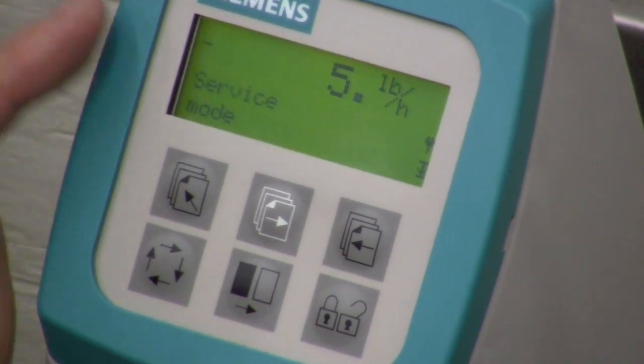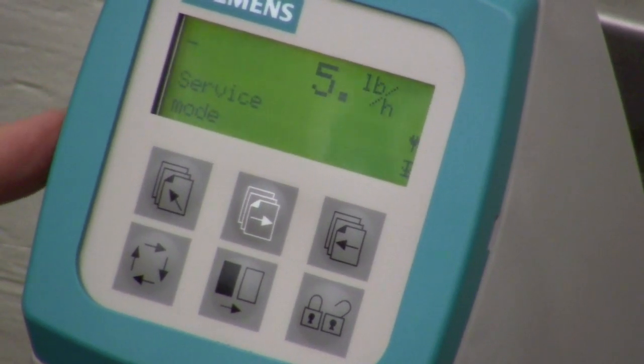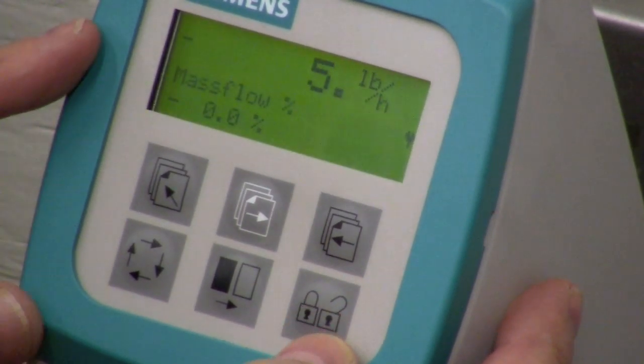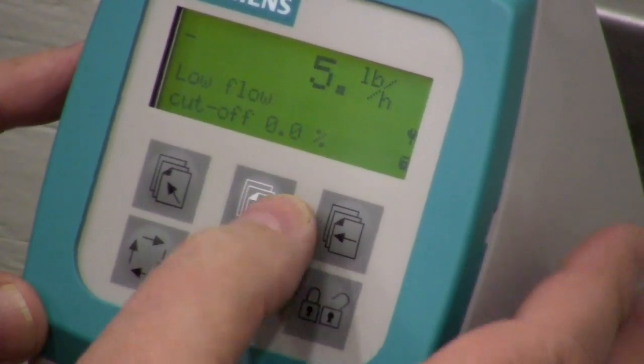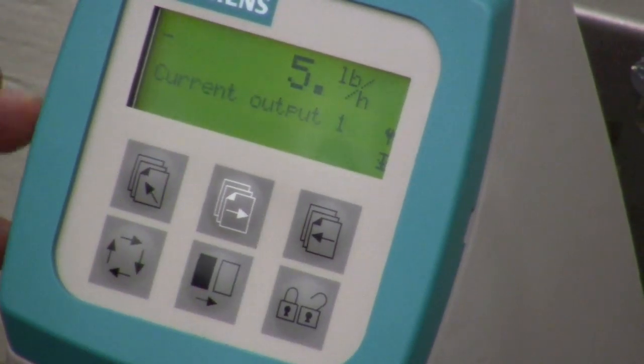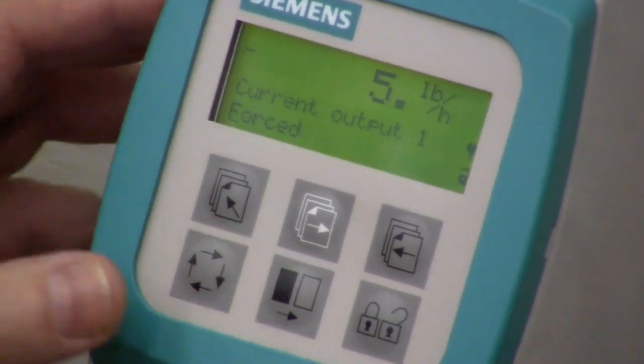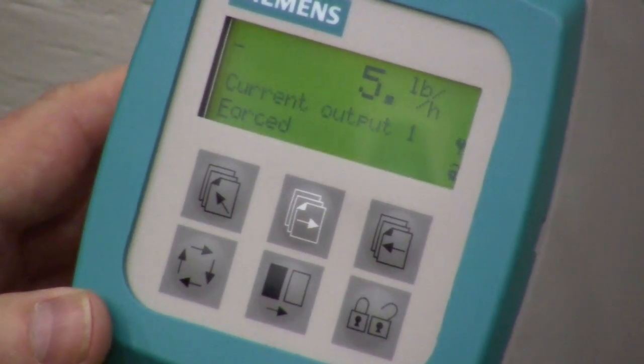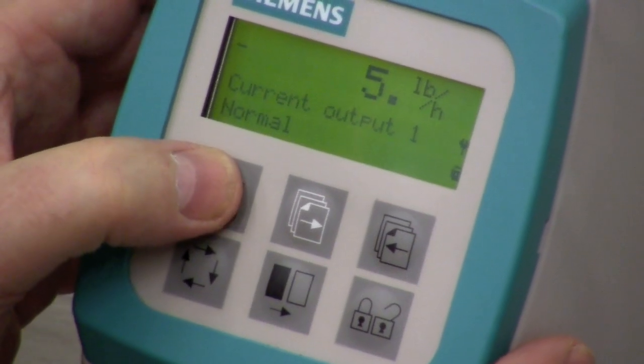The last mode I want to talk about is the service mode, which can be very useful once you've set up the instrument and want to test your outputs. Go to service mode and unlock. It tells me what my mass flow is and what the low flow cutoff is. Here's the best part — for current output number one, you unlock it and it says normal. If you change it, you can force 20 milliamps right out of the device, so you can test your downstream and make sure everything is connected properly.